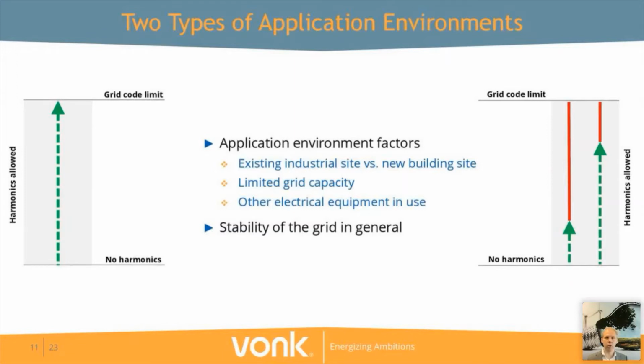Any kind of electrolyzer that you link to a public grid needs to be compliant to grid code requirements at the point of contact. If you are in an environment with less harmonic influence, for instance, when you're located at a new building site or located closely to an electricity plant, the amount of harmonics that you're being allowed with your power supply is equal to the grid code limitations. Or in other words, the grid code limitations become your minimum requirement. If your electrolyzer and its power supply is located in an environment where there is already harmonics influence from the environment, for instance, at an existing industrial site where there is limited grid capacity, or where there is already existing electrical equipment in use that's causing harmonics, you have less harmonics being allowed for the electrolyzer. This is reflected with the red bars that you can see on the right of your screen.